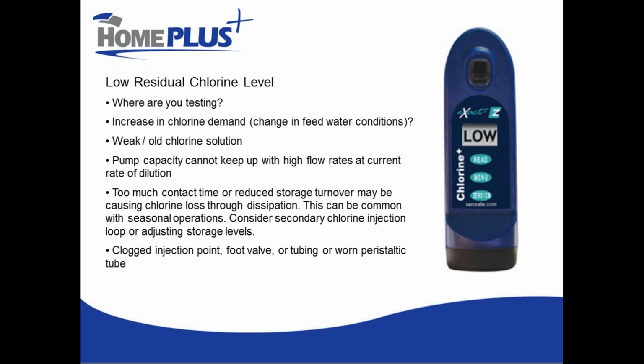So if you're having a problem where you're running water and your chlorine pump isn't even trying to inject, you may want to look at your water meter as the problem. Seasonal changes can sometimes lead to low turnover in a storage reservoir.